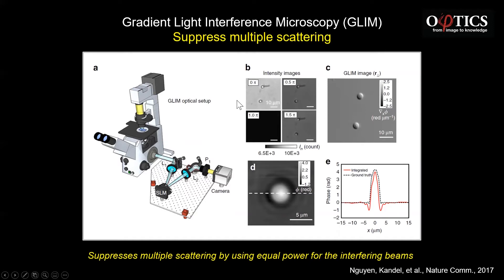This module controls the phase between one image and the slightly shifted one. With no phase shift you get the regular DIC. But once you add pi/2 more and pi/2 more, you create independent intensity images that can be combined to give a quantitative gradient, which can be integrated to become a quantitative phase map.